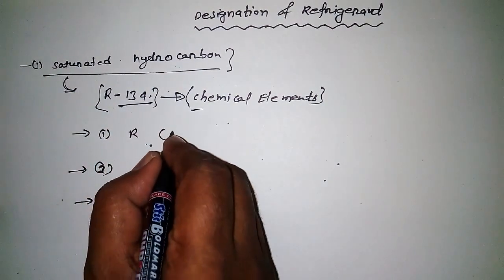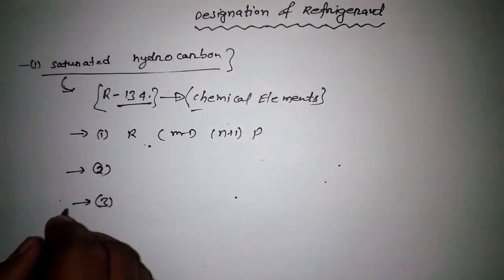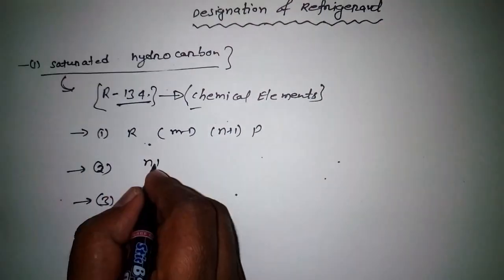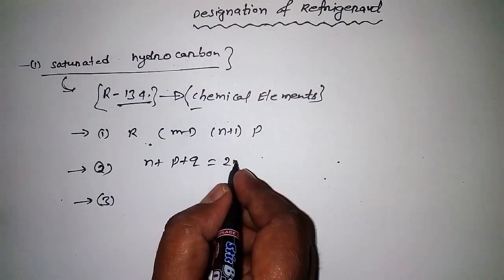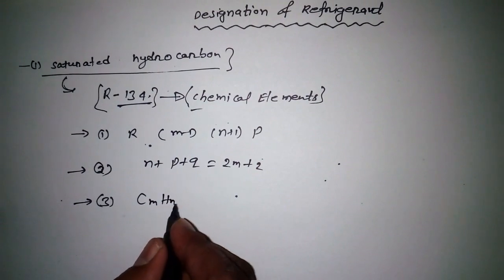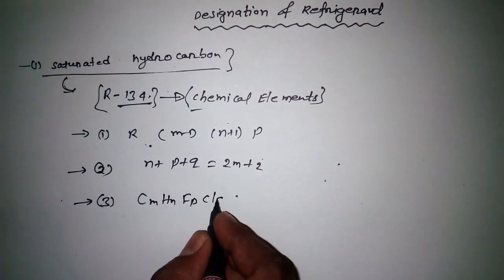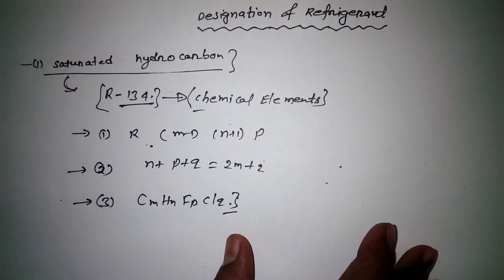First, you need to remember the formula: R(m-1)(n+1)p. Another formula: n + p + q = 2m + 2. And finally: C_m H_n F_p Cl_q. This last one is also useful for other refrigerant designations.